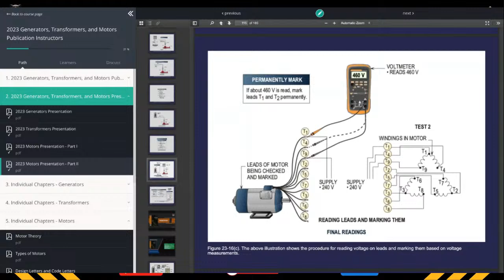I'm going to show you something else cool. Go look and see if you can find this. This is where we get into motors, and we actually show you how to do fire pumps. Say here's your fire pump. We'd show you the secondary currents here, where you have locked rotor current, full load current, and other loads. Then right here, we show you how to calculate overcurrent protection for a separate drive system, and here's one without it, showing how to calculate it for sizing your overcurrent protection device. That's set up to make sure the motor will continuously run. Basically, that overcurrent protection device is going to hold. The motor will burn up before it trips.